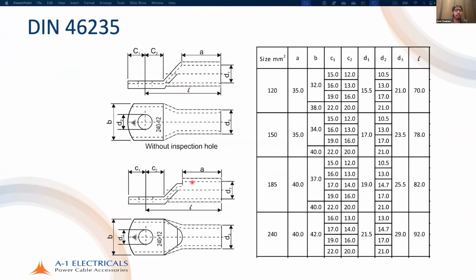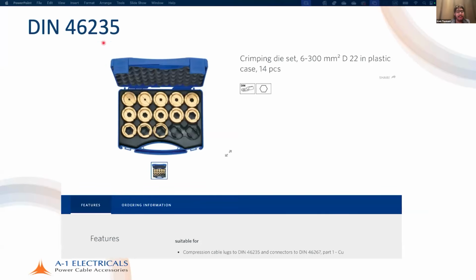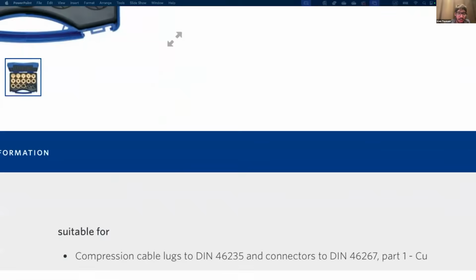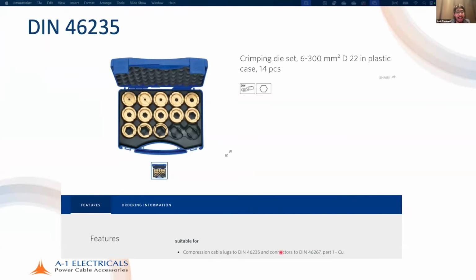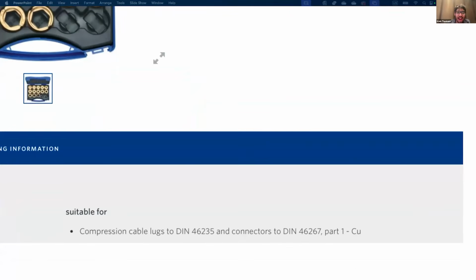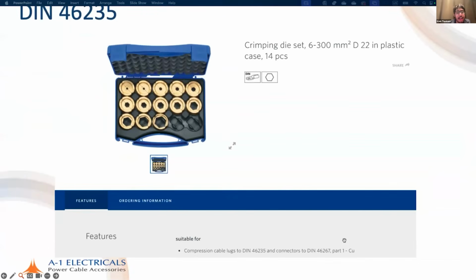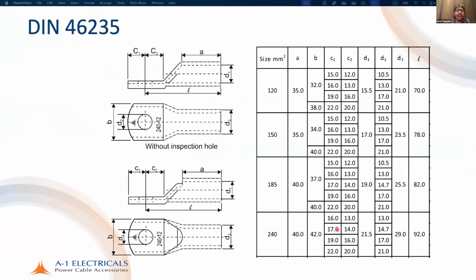See, DIN 46235, for instance, provides all of these dimensions, and that allows for standardization with the crimping tools. If you go to a manufacturer, for example, and purchase a die set for DIN 46235, for example, this one is DIN 46235 and 46267 Part 1. This will be dimensionally compatible with the DIN lug. So you are ensured that you get a good electrical connection because the crimping is done correctly.